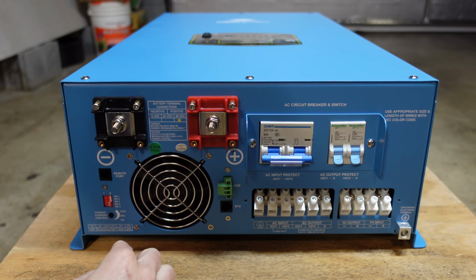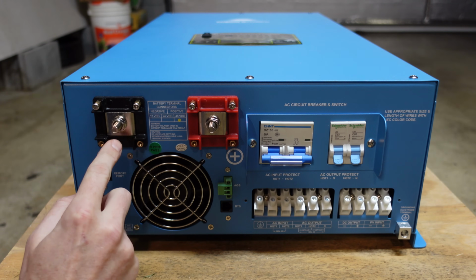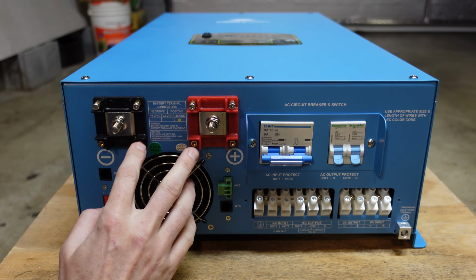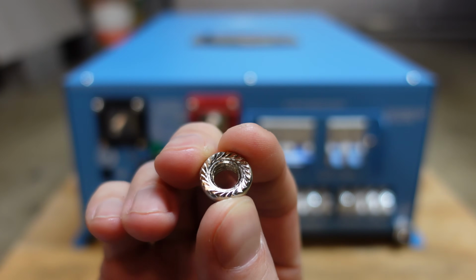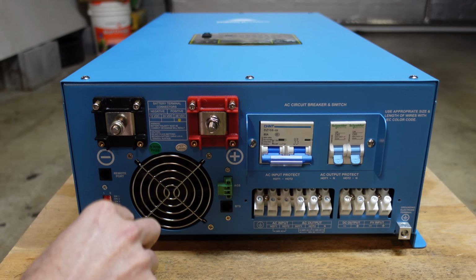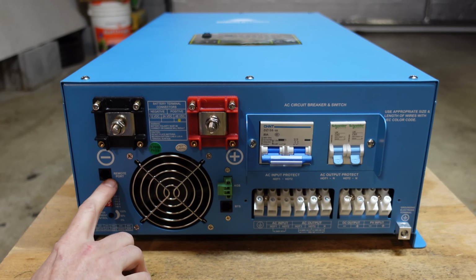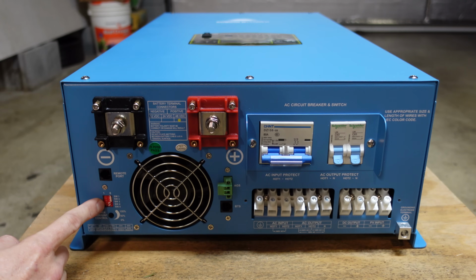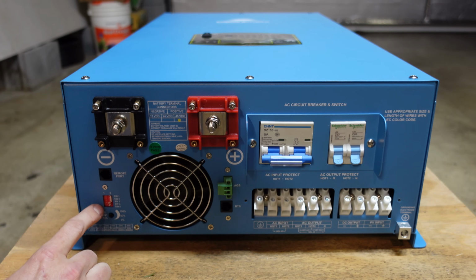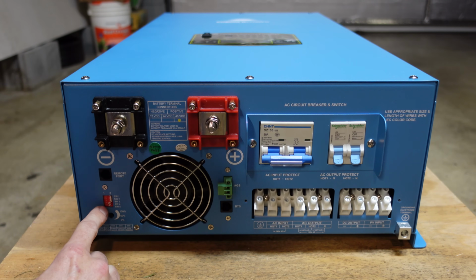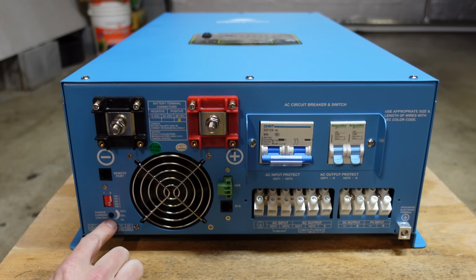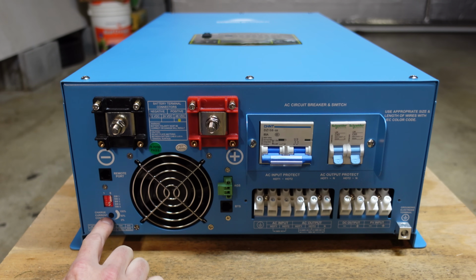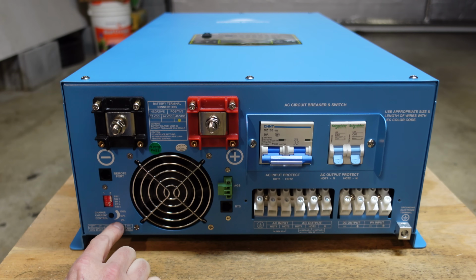Alright, so taking a look at the bottom of the inverter where all the fun stuff is, here we have the main negative and positive input terminals for the 48 volts DC, and they've got some nice serrated flange nuts here for connecting those. We have the remote port where our remote on-off switch will connect into. We have 5 small DIP switches. These will control things such as the frequency. This can do both 50 and 60 Hertz. It will also control battery trip points, power saving configuration, and we have a small dial here on the bottom left for controlling the charge current, and this does contain a 100 amp AC charger, so that's going to be 0 to 100 amps, fairly easy there.